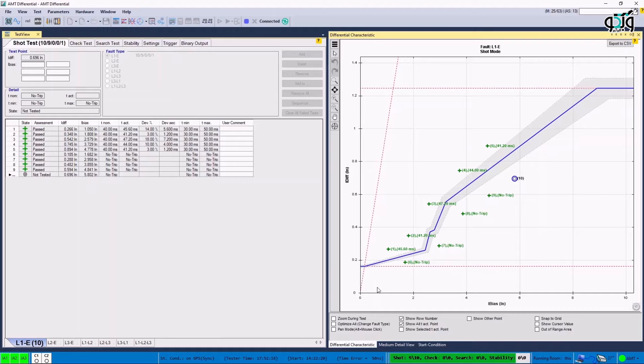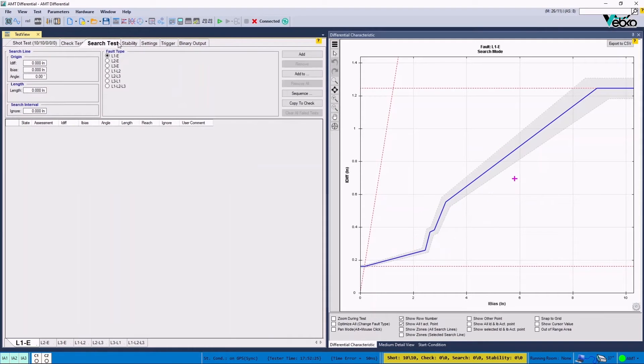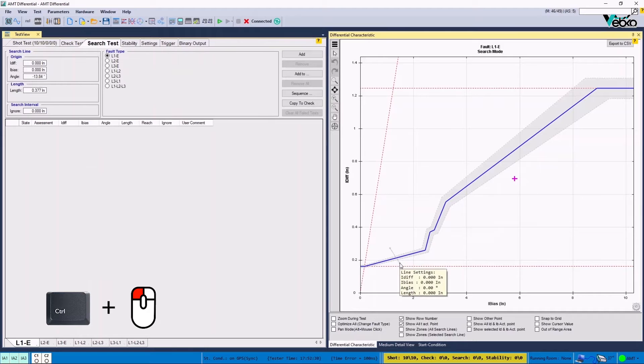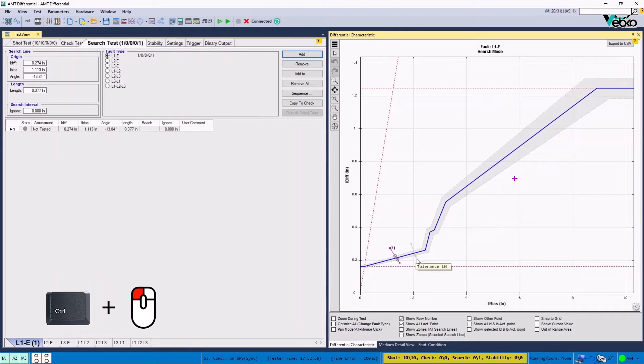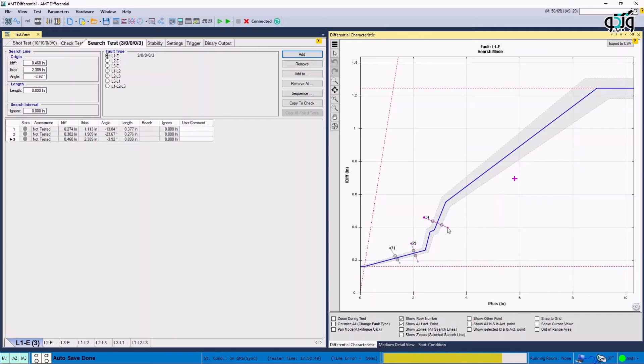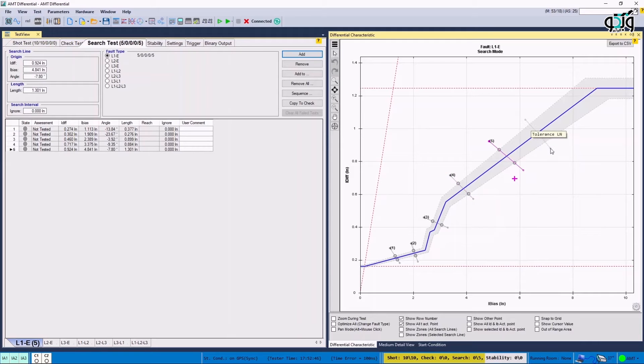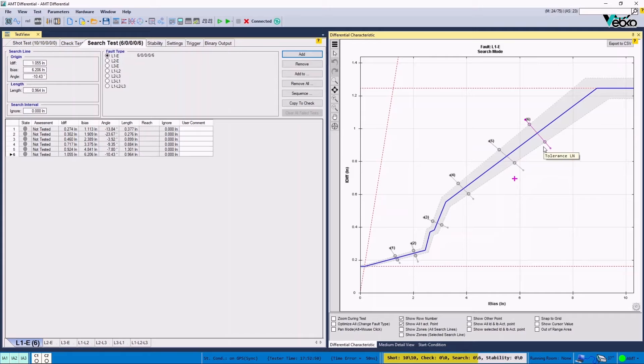To perform the search test first, it's necessary to draw lines called search line in different parts of the vector. To draw a search line, the user can hold control button and left click of the mouse on differential characteristic window and then move the cursor on the characteristic curve as intended. It can be seen that the information regarding the drawn search line is displayed in search test lines table. After drawing these lines, it's necessary to share the information of these lines with the other side so that the drawn lines are exactly the same on both sides and they both have the same order.